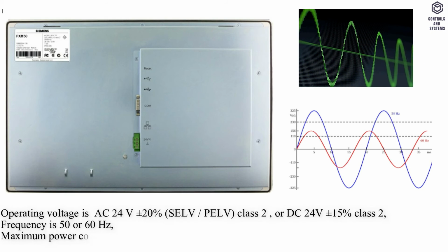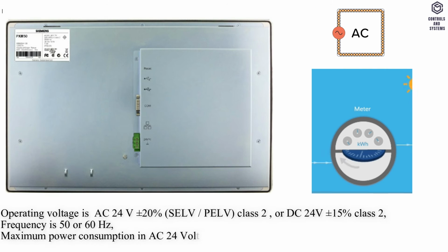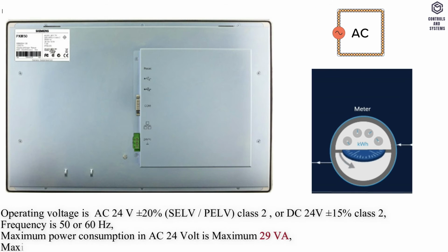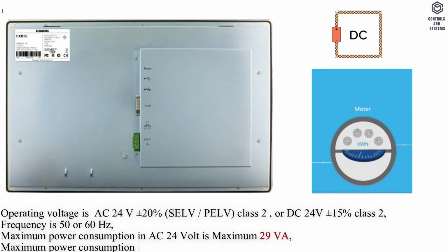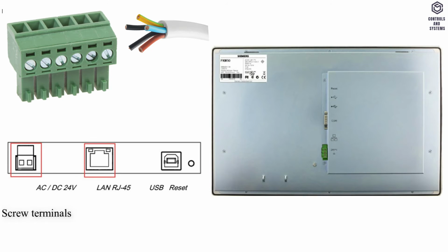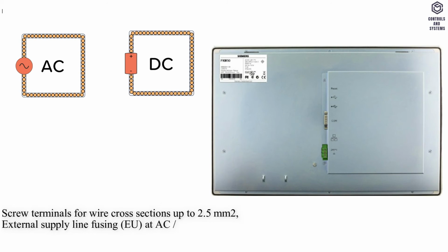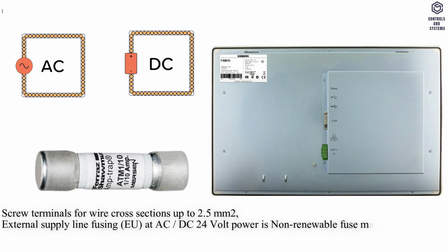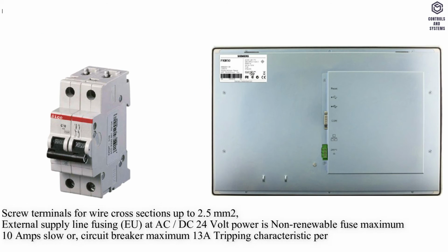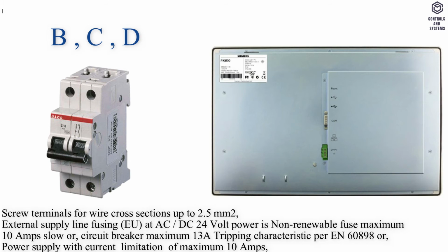Frequency is 50 or 60 Hz. Maximum power consumption in AC 24 volt is maximum 29 VA. Maximum power consumption in DC 24 volt is maximum 17 watt. Screw terminals for wire cross sections up to 2.5 square millimeters. External supply line fusing, EU, at AC, DC 24 volt power is non-renewable fuse maximum 10 amps slow or circuit breaker maximum 13 amps tripping characteristic B, C, D per EN 60898, or power supply with current limitation of maximum 10 amps.